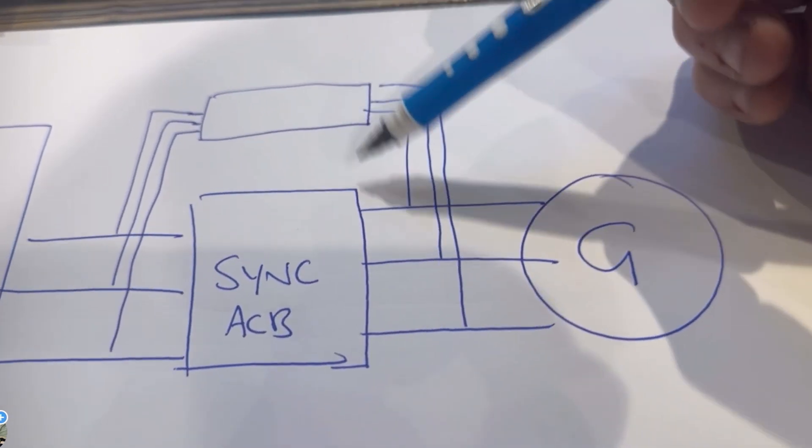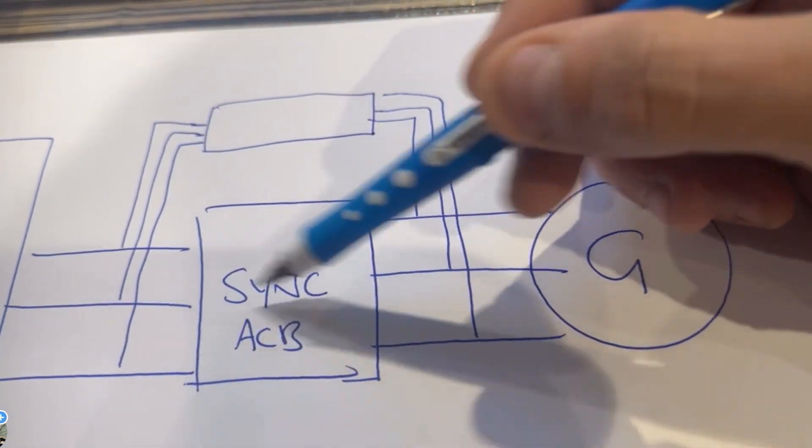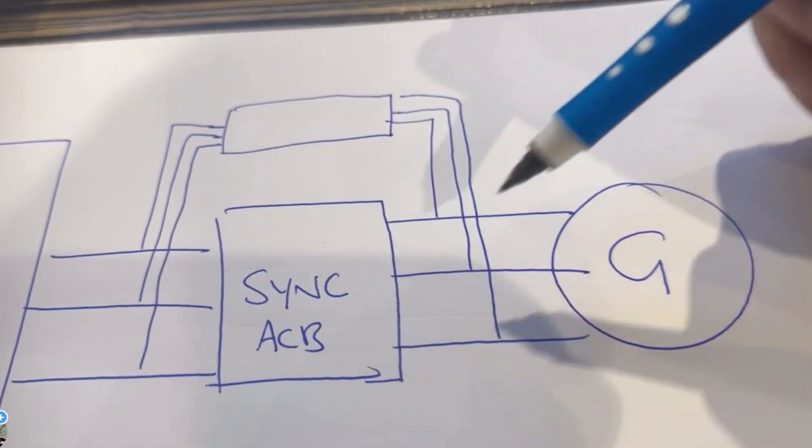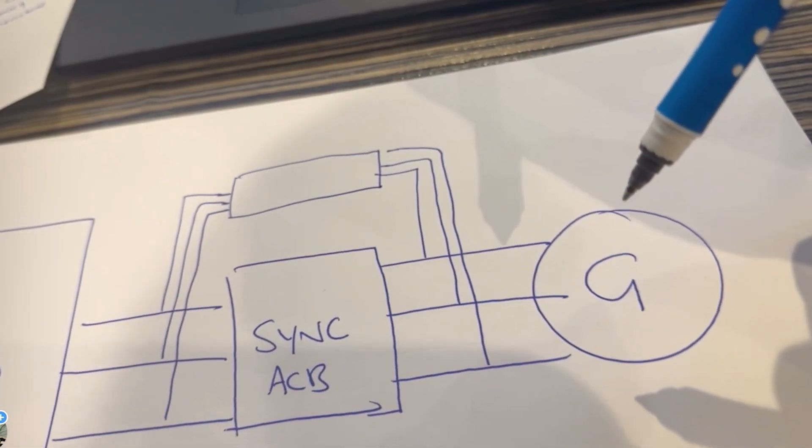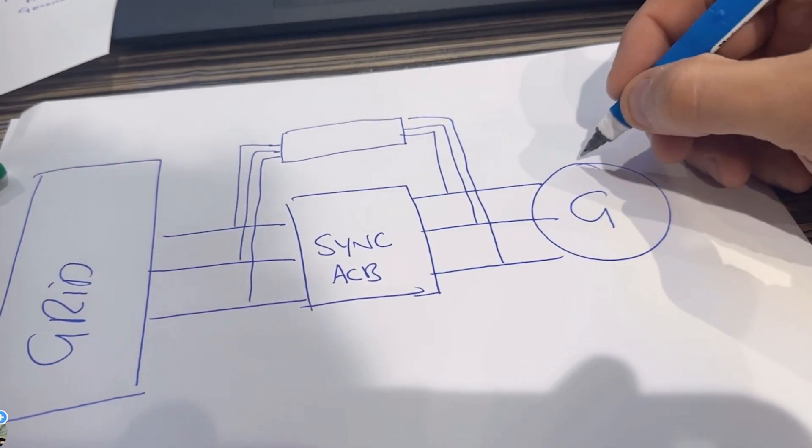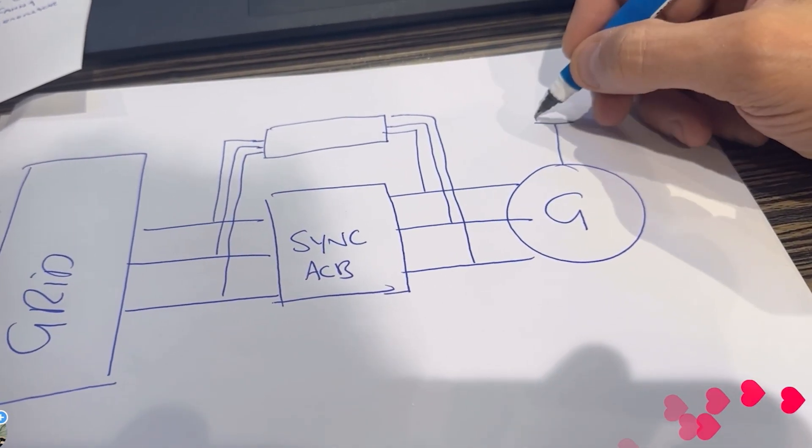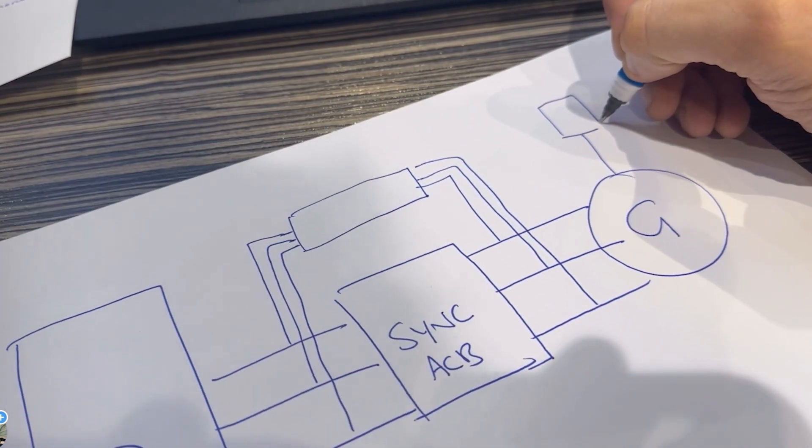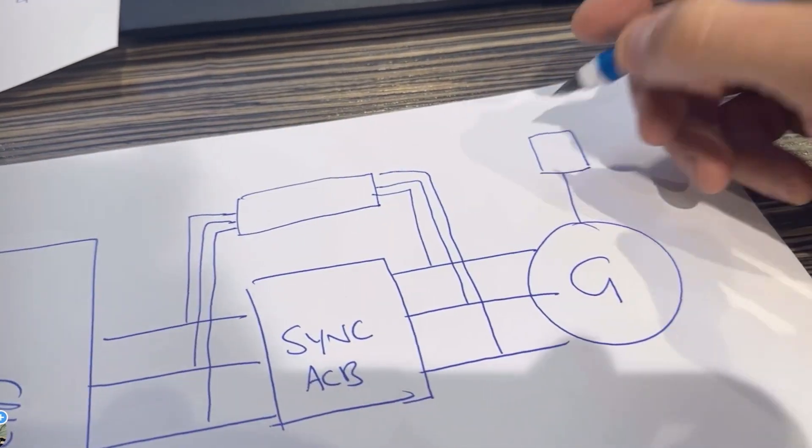This looks at this voltage and phase and rotation, and this looks at this voltage and phase and rotation. It makes sure for a start that they're the same, so that when this breaker closes it doesn't blow one side up or basically fuck your generator, just to keep this simple.